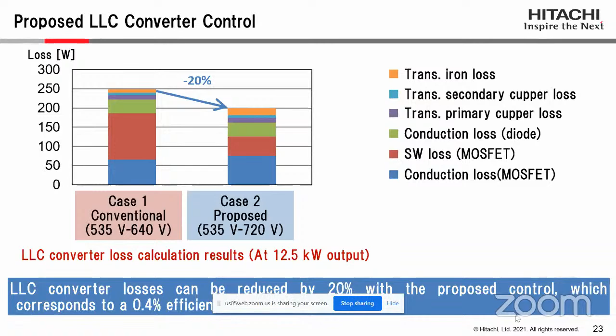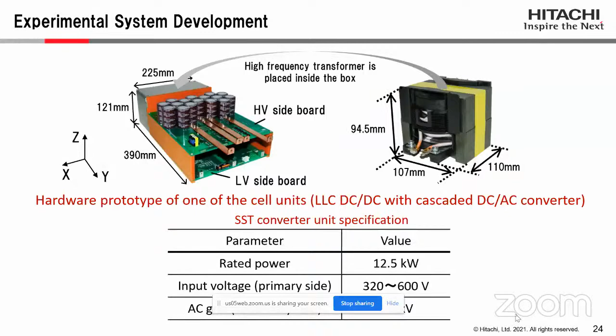Related to this cell unit design, there are two challenges. One is the high frequency, high power transformer design, including its insulation. The second challenge is the type of DC to DC converter — what is the best solution, DAB type or LLC type? This depends on the application: if we need high voltage variation, DAB may be the best solution; if we need efficient operation with a fixed bus voltage, LLC could be a better option compared to DAB type.